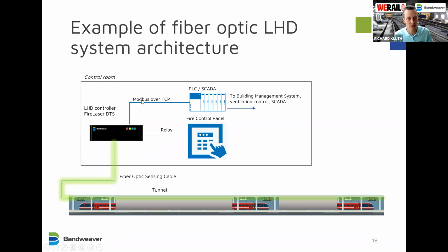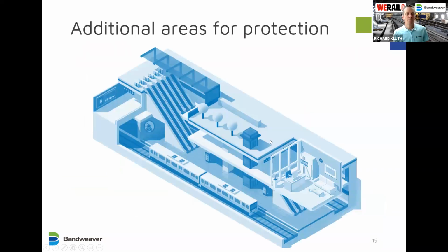And Modbus over TCP/IP typically, which is either to the building management system, ventilation control, or SCADA system, and that carries more information. There you can get the absolute temperature, the absolute alarm value, the distance. So as we see when we go later, you can get much more benefits from that additional information. So we've talked about tunnels, but what we're increasingly seeing is that operators are tending to use this in other parts of the network as they understand the flexibility and the benefits of this.